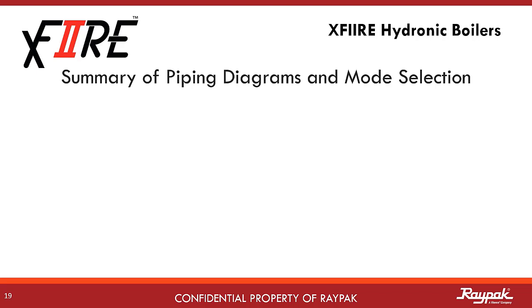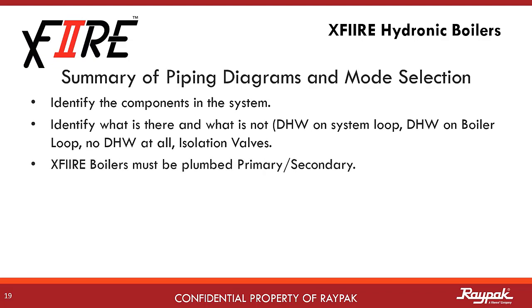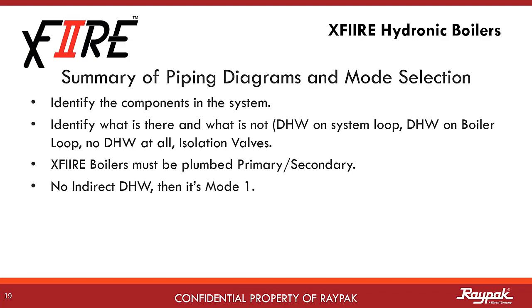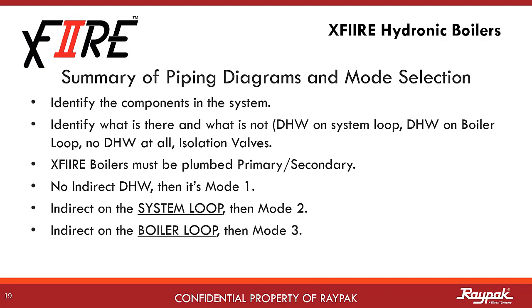Here are some overall pointers on plumbing systems and how they relate to mode selection for type H boilers. Identify all of the parts of the system and look for what is there as well as what is not there. Make sure it is plumbed primary-secondary. In most cases, with no indirect domestic hot water present, Mode 1 will be your choice. If you have an indirect domestic hot water tank present on the system loop, then it's Mode 2. If the indirect domestic hot water is present on the boiler loop, then it's Mode 3.